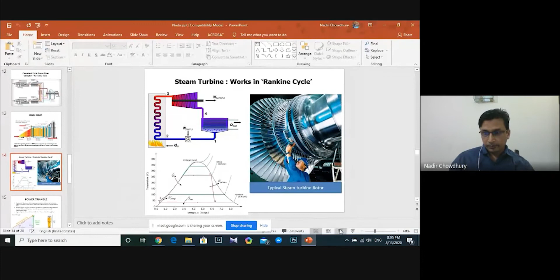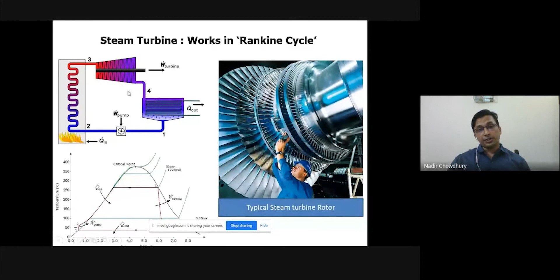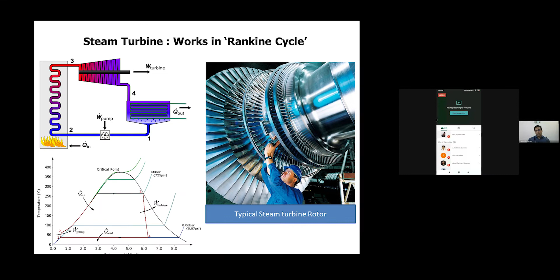The steam turbine works in the Rankine cycle. In the upper diagram, you see the unit that extracts water, a big water reservoir we call the condenser, then a condensate pump. It pumps water from the condenser to the HRSG, which produces steam from the water, and that steam is thrown onto the steam turbine blade, converting heat energy into rotational energy. With that shaft, the steam turbine generator rotor is connected, so that also produces electricity. On the right side diagram, that is the typical steam turbine rotor, with blades through which steam passes, causing rotation, acting as the prime mover of the steam turbine rotor.